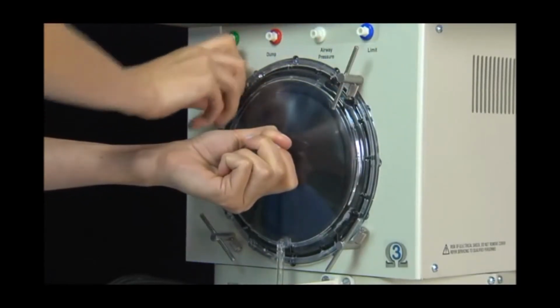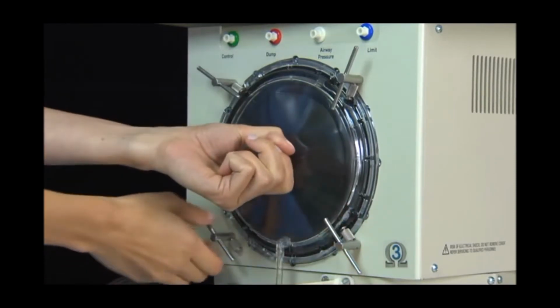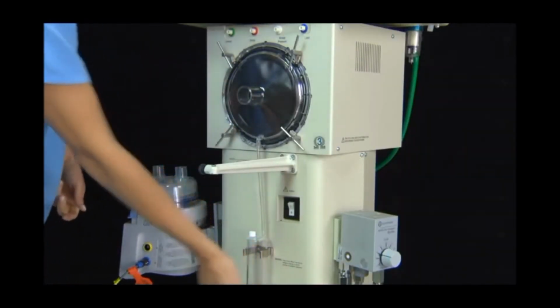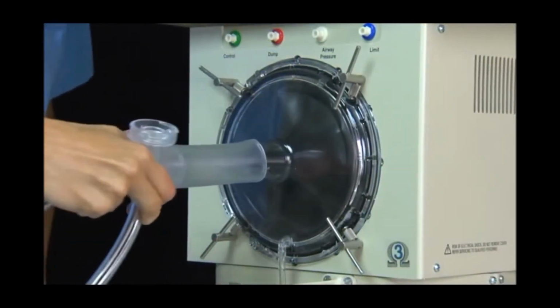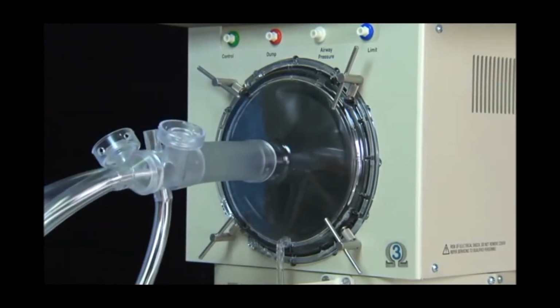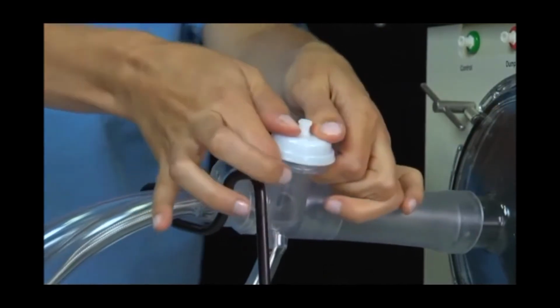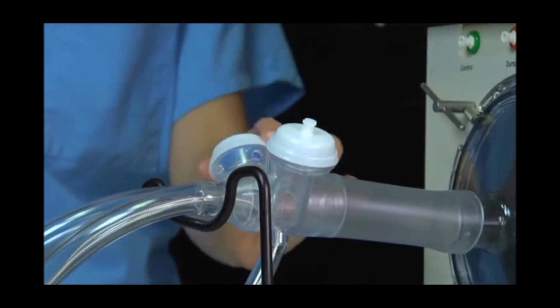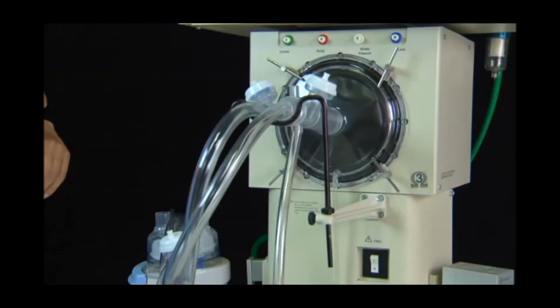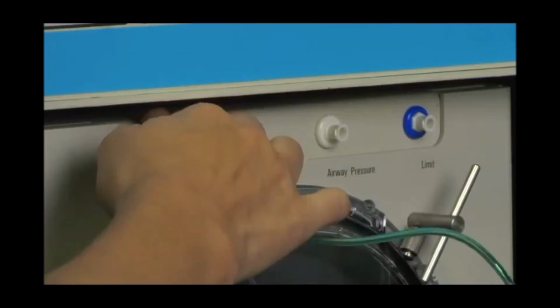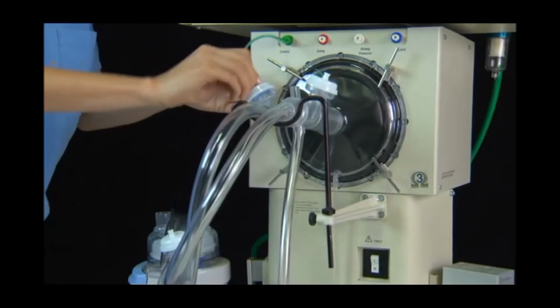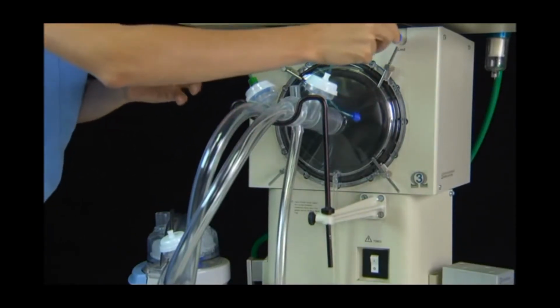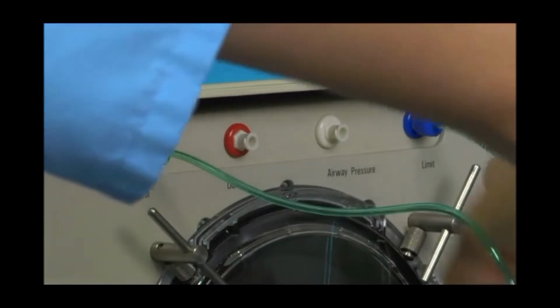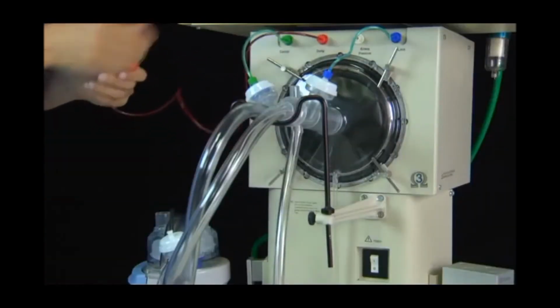Circuit Setup Procedure. Attach the bellows water trap assembly using the 4 T-handle quarter-turn fasteners. Snap the water trap into the metal clip on the front of the ventilator body. Connect the circuit body to the central port on the bellows water trap. Snap the 3-cap diaphragm assemblies onto the valve bodies located on the patient's circuit. Attach the 3 color-coded tubes to their corresponding valve caps. Green to the mean airway pressure control valve, located on the expiratory limb of the circuit opposite the limit valve. Blue to the limit valve, located on the inspiratory limb of the circuit directly in front of the driver. Red to the dump valve, located near the middle of the expiratory limb of the patient circuit.